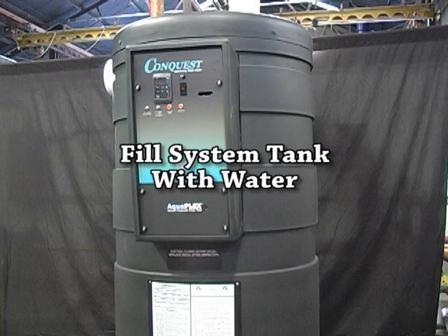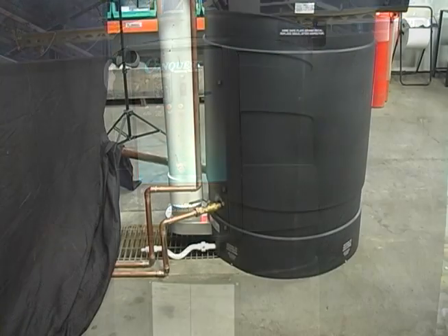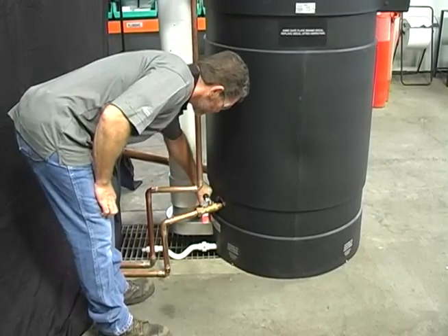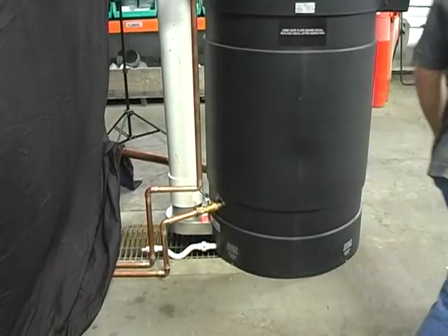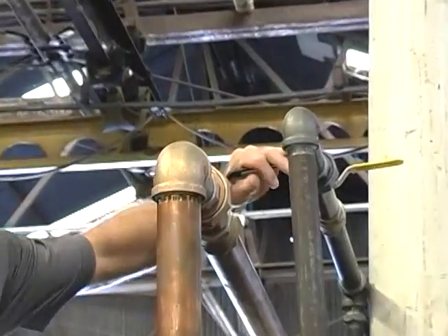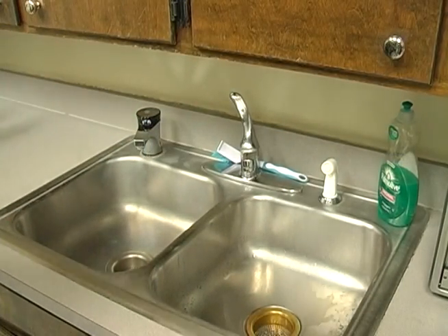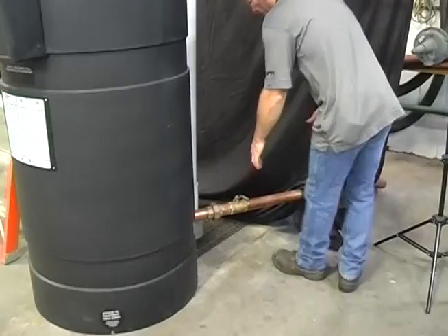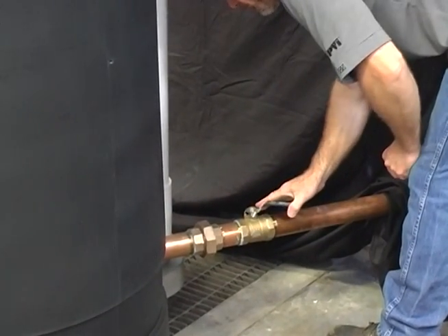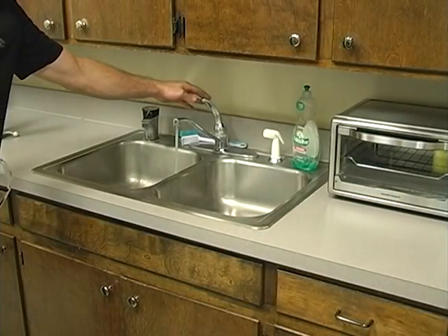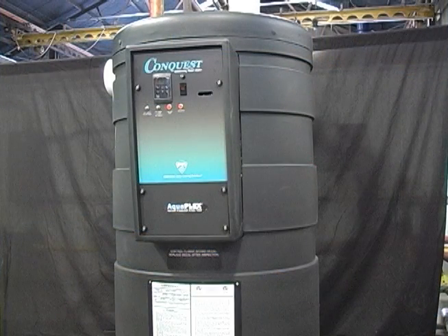Prior to startup of the burner, the tank must be filled with water. Begin by fully closing the drain valve. Open the shutoff valve on the hot water outlet pipe from the water heater. Open a nearby hot water faucet to allow the air to escape when filling the storage tank. Start filling the tank by fully opening the isolation valve on the cold water inlet piping. A steady flow from the nearby hot water faucet indicates that the tank is full. Shut off the faucet. After filling the tank, check all tank connections to ensure they are watertight and tighten any as necessary, as leaks at the tank fittings will damage the insulation.